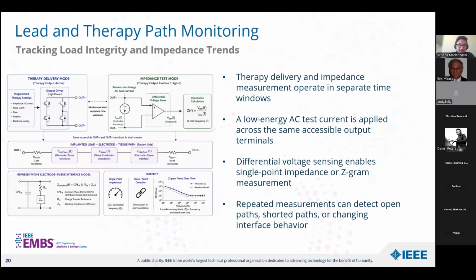The same measurement can also be repeated across several frequencies if you want to create a Z-gram that provides a much richer view of frequency dependent behavior of the electrode and the tissue path. But the greatest value often comes from looking at the trending, right? Comparing it to the previous behavior. So a single measurement gives us a snapshot. So repeated measurements can reveal gradual degradation or changes in the lead and the electrode to tissue interface before we even develop any clear open or shorts.